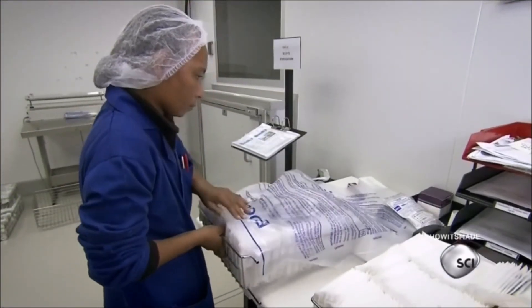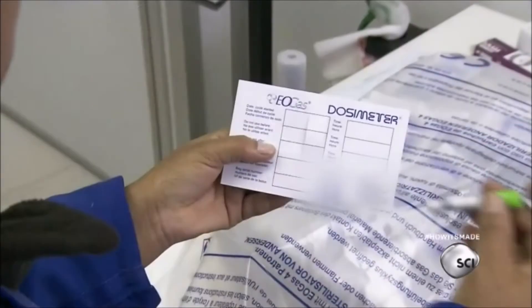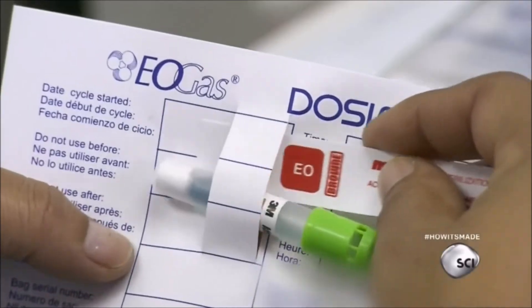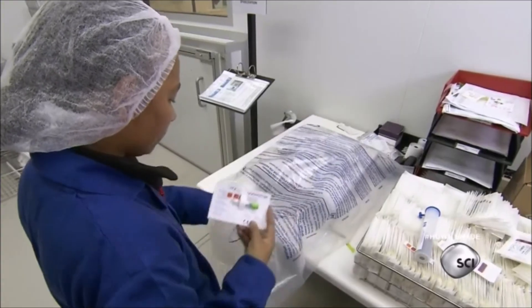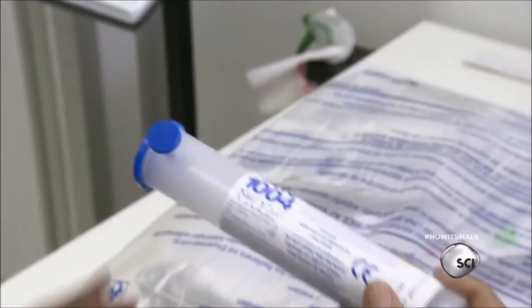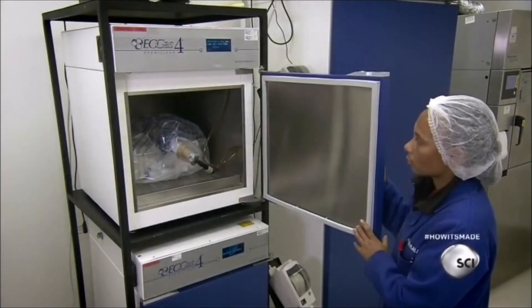The finished product is sent for terminal sterilizing. A worker places the basket into an ethylene oxide, or EO gas, sterilization bag. She attaches a biological indicator vial and a control strip on a sterilization control card and puts the card inside the bag. She then adds an EO gas delayed release canister in the bag and places the sealed bag into the sterilizer.